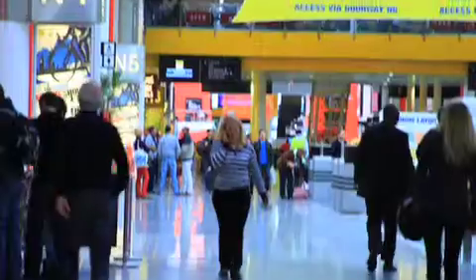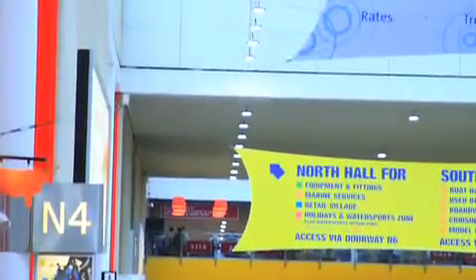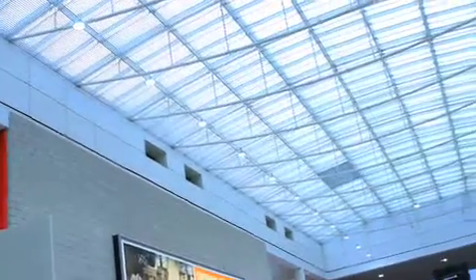The type of lighting has made the venue and the building look bigger. It's made it look cleaner. There are so many wins and very few negatives. One of the biggest problems we had with sodium fittings was the fact that with different ages of light fittings, you've got different colour renders. When phase two opened, phase two has got quite a lot of light harvesting with ETFE roofing. Now we couldn't actually start cutting holes in the roof down this end to produce ETFE natural light harvest, so we had to try and find lighting that was going to match that outside viewpoint.